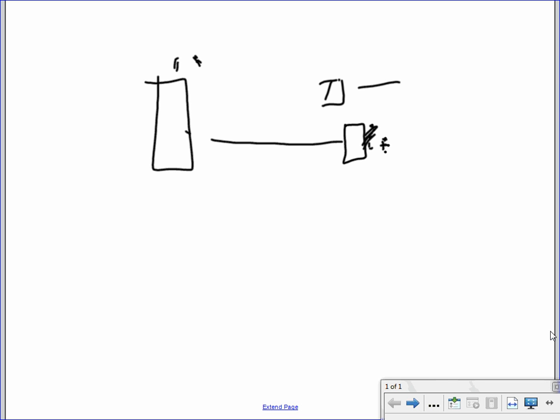And the pilot relay is simply there to provide isolation from the low voltage fire alarm system to the high voltage air handling unit power. Okay? Make sense? So yes, relays are involved, but logic is also involved, because an addressable intelligent fire alarm system is software driven. You have to program it. This device has an address in the system, and this device has an address in the system. Then you write logic equations for all of the functionality.